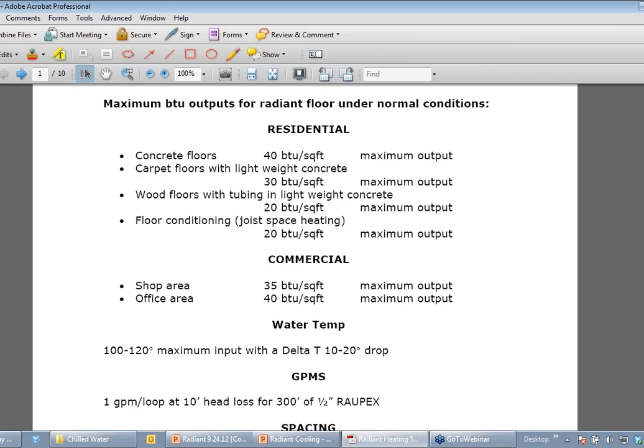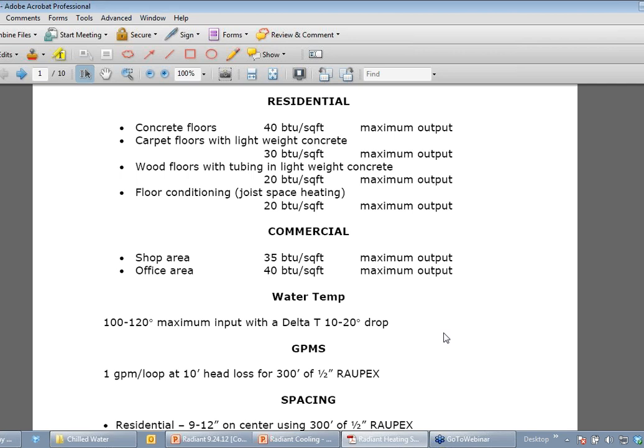But residentially speaking, if you're putting it in a concrete floor, you could probably expect to get about 40 BTUs per square foot, versus if you're putting it into some kind of lightweight system like wood flooring, or between the joists in a retrofit, you're probably only going to be able to get half of those BTUs out of the system. Commercial, similar kind of thing. We're going to get up to about 40 BTUs. Water temperatures, like I said, you're probably going to have 115, 120 at the absolute max. It's much more common to design things in the 100, 105, 110 degree range. And then you'll use an outside air reset schedule to actually run it between, say, 85 and 110 or something like that.